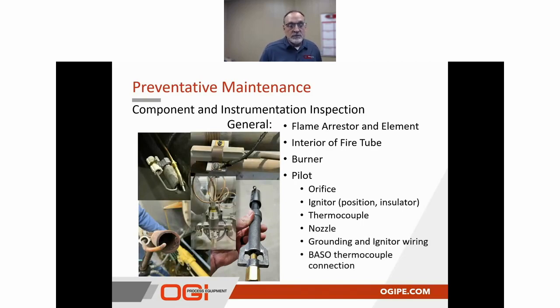Here we're going to inspect the ignition rod. Is the pilot nozzle clean, and is again the orifice clean on the pilot? We want to make sure that if there's a sensing rod, that it is also clean and properly aligned, and that the ignition wires and the ground wires are tight and well connected to the pilot assembly. And then from that, if there's any issues that we see, we're going to go ahead and make those repairs. Additionally, we're going to ensure that the BASO thermocouple connections are properly secured to both the BASO and obviously the head of the pilot.